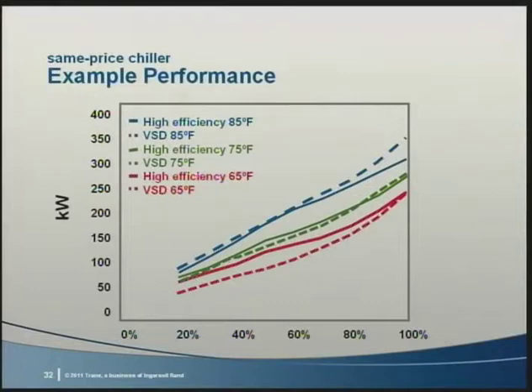The chiller we were replacing was 700 tons. Based on our review of the building loads in the present configuration and expected future use, we right-sized the chiller capacity from 700 to 600 tons. Now here's the performance of two same price chillers, one with a drive and one without. If this graph looks unfamiliar to you, note that the axis is kW, not kW per ton. You actually pay for kW, not for kW per ton.